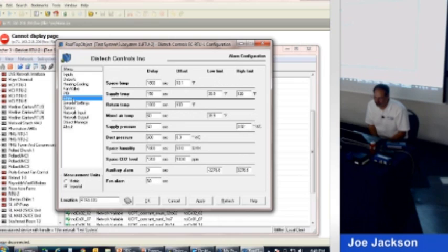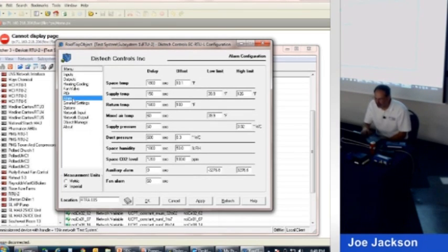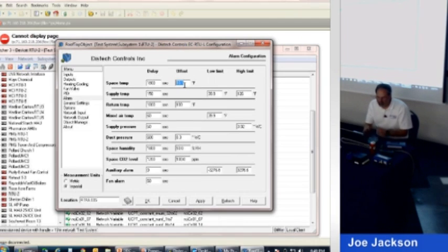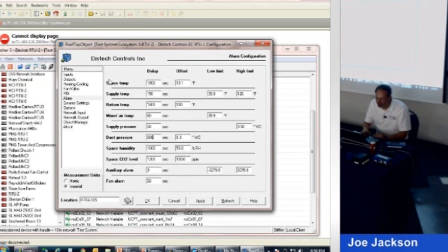Alarms. This thing will auto-generate some alarms if the space temperature is more than 10 degrees below set point for 1800 seconds, but you can change it to whatever you want it to be. The nice thing about this is if it goes unoccupied and it goes down to 60 degrees, it's going to throw an alarm when it hits 50 degrees for 1800 seconds. So it's not going to generate any nuisance alarms. They should all be real. If you don't have the sensor like duct pressure, we don't have a duct pressure sensor, it'll ignore the alarm if there's no sensor there for it. So you can have it auto-generate some alarms if you'd like.